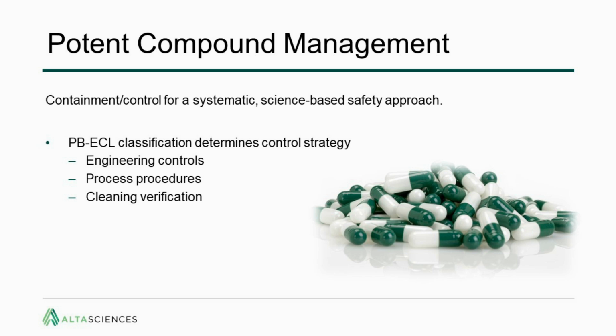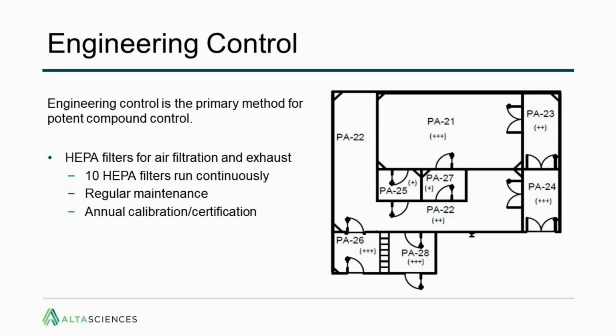Here is an overview of the layout of the room. Engineering controls are the primary method for handling potent compounds—HEPA filters for air filtration and exhaust, and you can see each room is HEPA filtered, with regular maintenance and annual calibration and certification of the HEPA filters. It's pretty small to see, but here we'll talk about the plus signs.